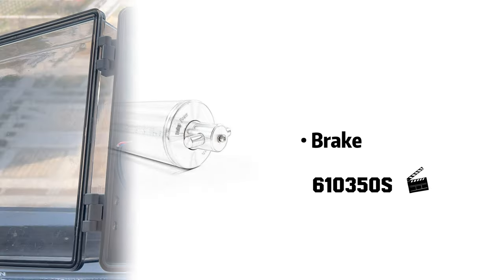When the overcurrent error information appears on the screen, how can we quickly identify and resolve the issue? The most common cause is a problem with the braking system. Here we take the 601140S motor for example.